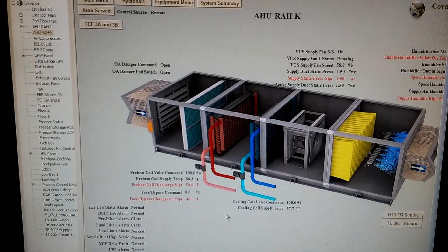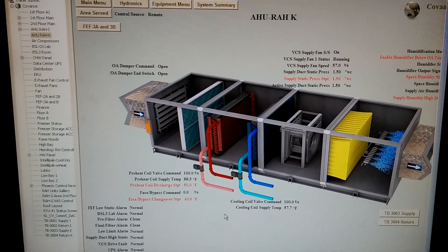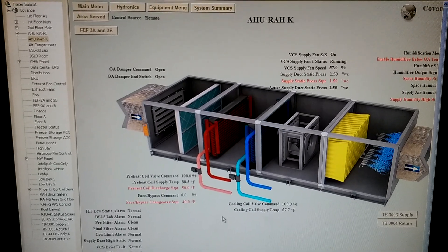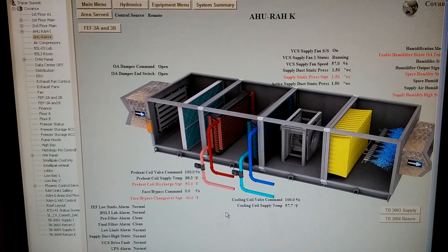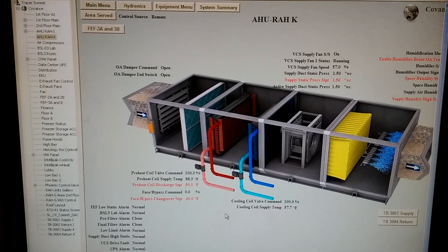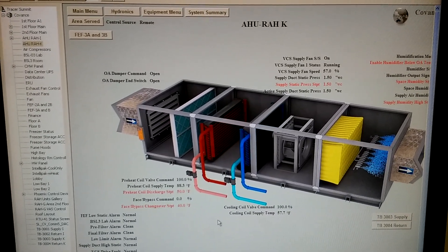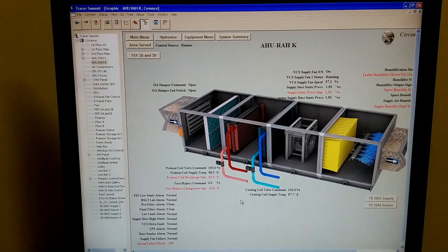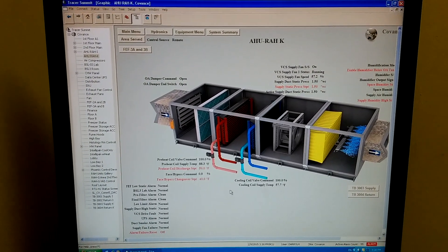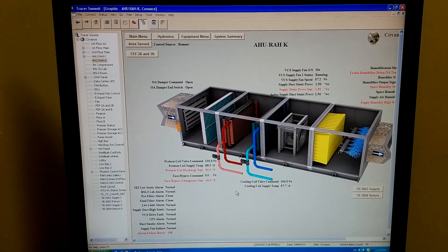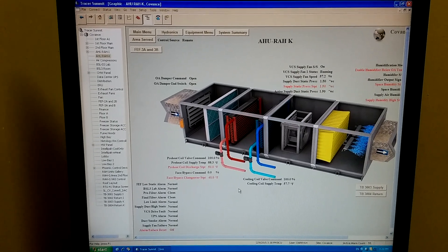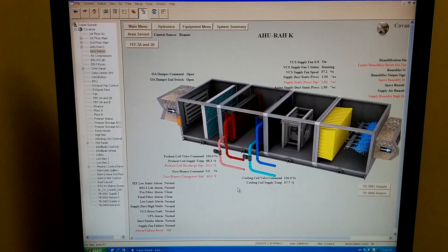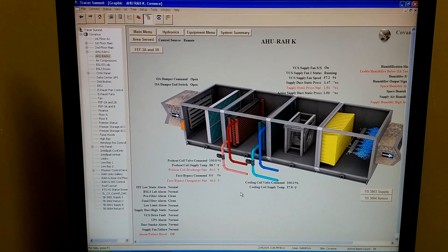Supply temp is 88 and my face and bypass dampers are at 100%. So what's happening is a low ambient cutout is tripping. I'm trying to figure out if the dampers are staying open when they should be closed or if they should be closing when they're staying open.